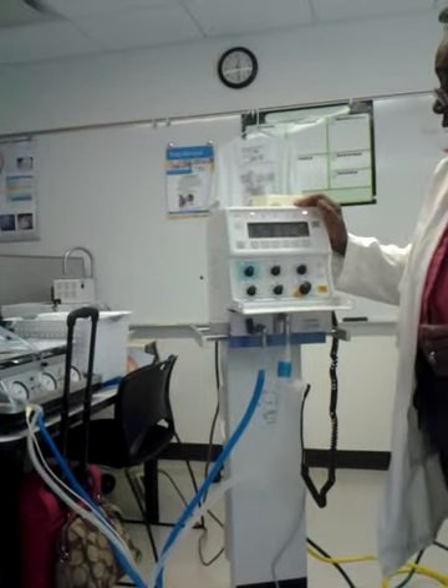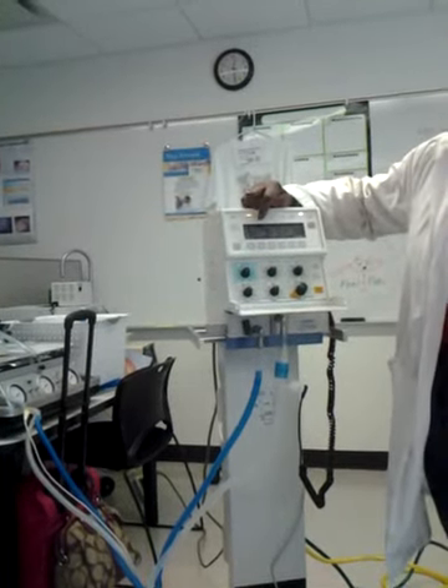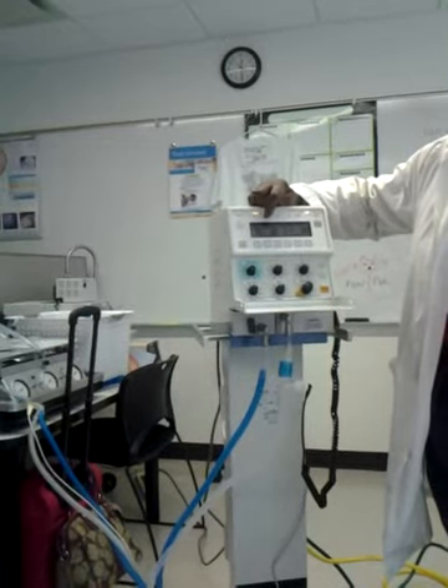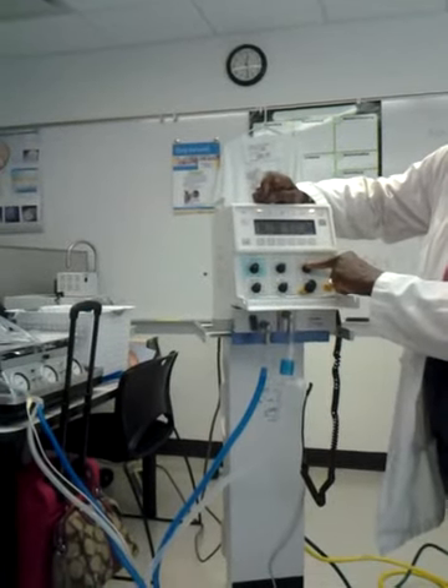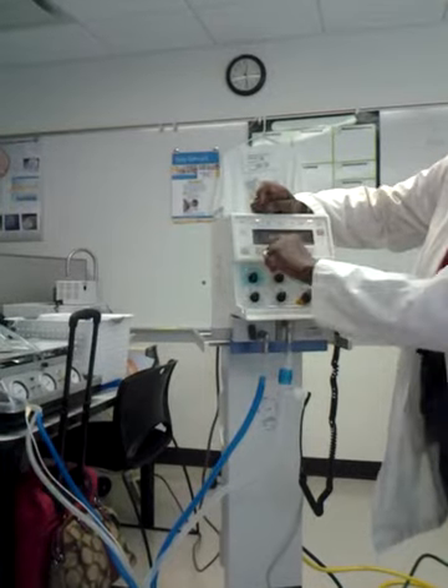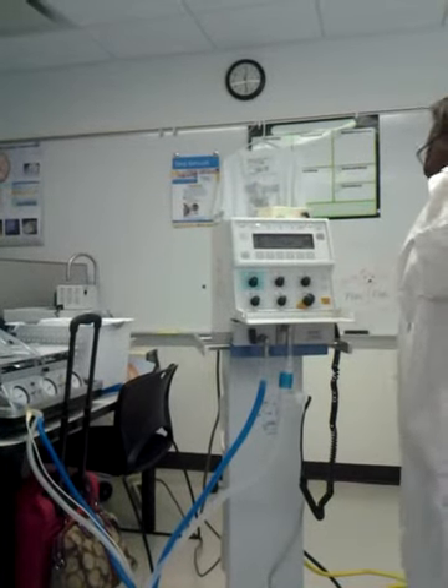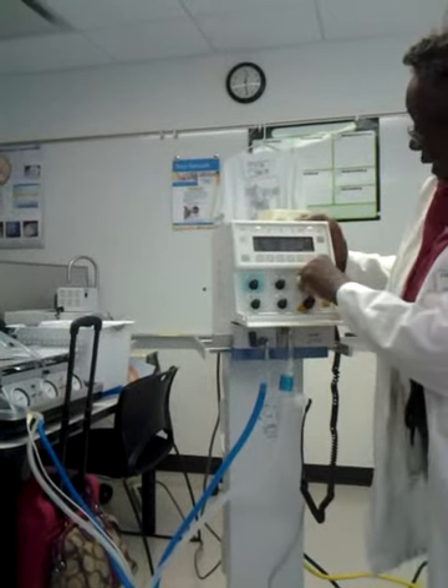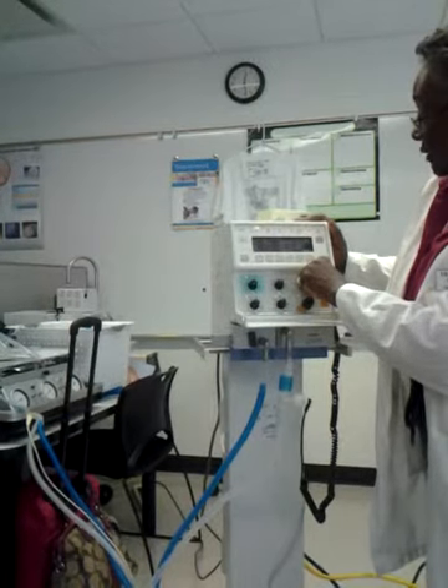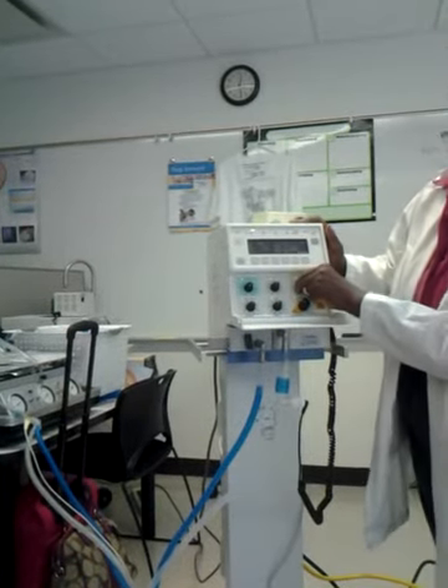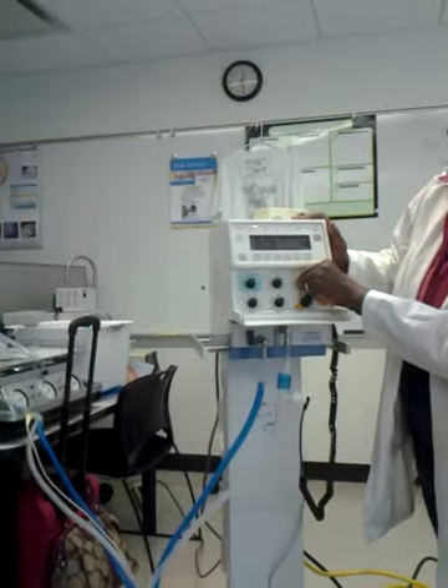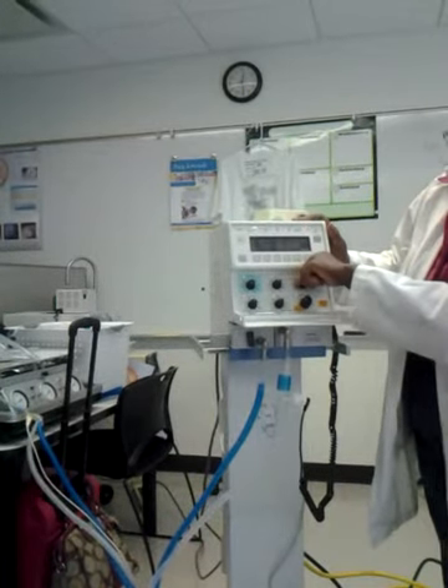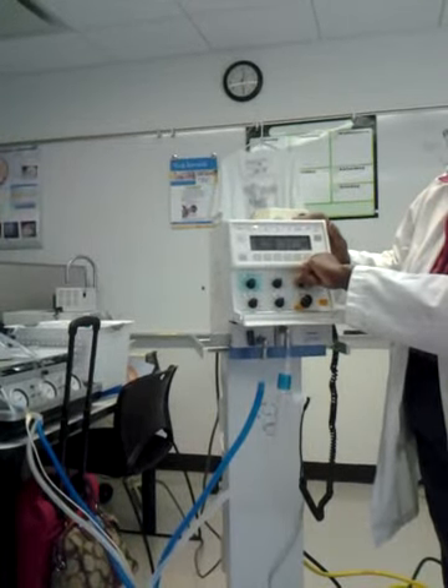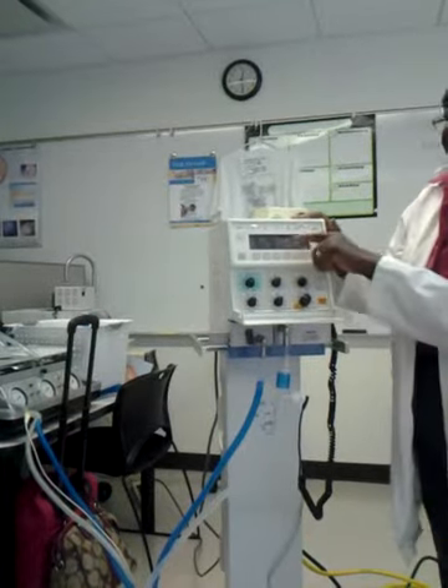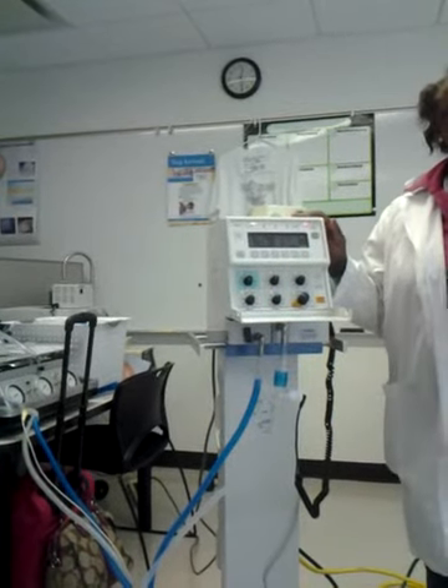Now I'm at 0.5. But my rate changed to 25. So now I would have to change my E time to get this back to 24. And whether or not you increase or decrease my E time, you see my rate's going up? If I increase my E time, my rate's going down. So now I'm back to 24 breaths per minute.